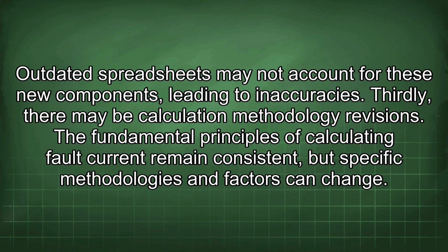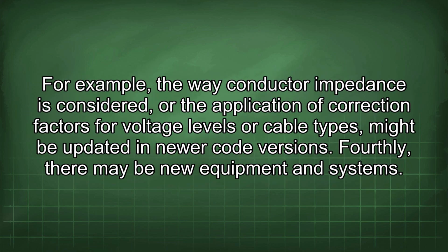Thirdly, there may be calculation methodology revisions. The fundamental principles of calculating fault current remain consistent, but specific methodologies and factors can change. For example, the way conductor impedance is considered, or the application of correction factors for voltage levels or cable types, might be updated in newer code versions.